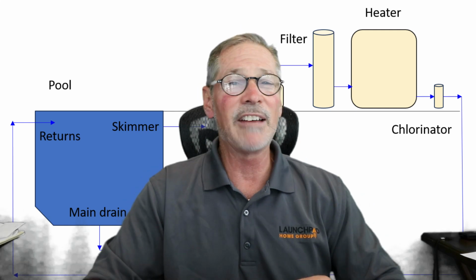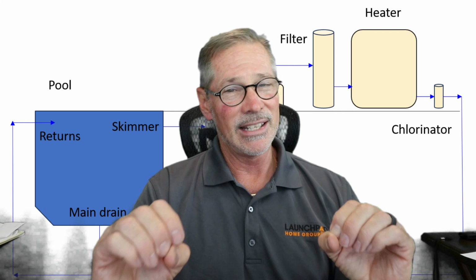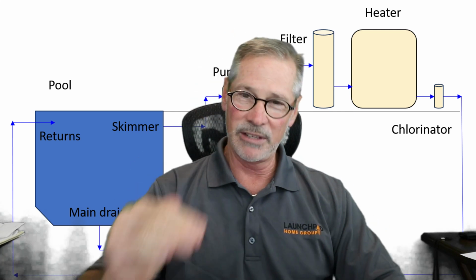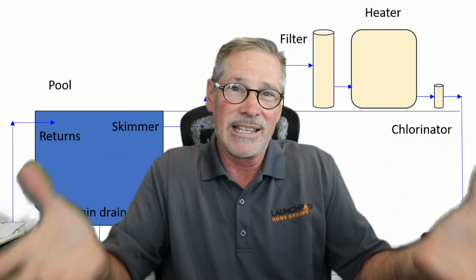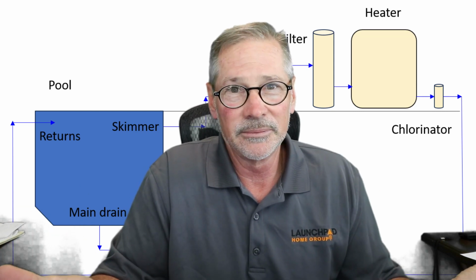If you still have bubbles after turning those valves off, then that's telling us the breach is going to be somewhere between the valve and the pump. But this is all easily accessible because it's all above ground and it's going to be a much easier fix.